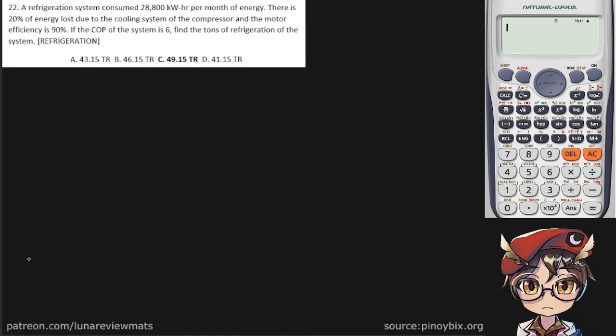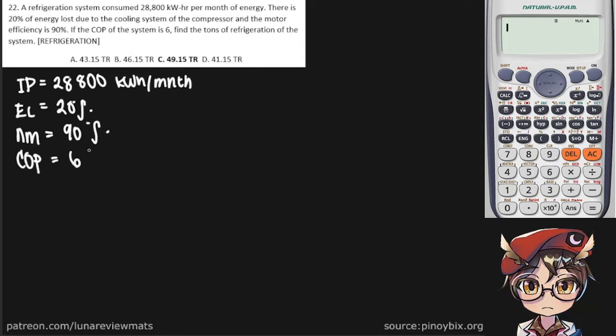A refrigeration system consumed 28,800 kilowatt hour per month of energy. Let's assume that's our indicated power. There is a 20% energy loss due to the cooling system compressor, and the motor efficiency is 90%. If the coefficient of performance, COP of the system is 6, find the tons of refrigeration of the system.